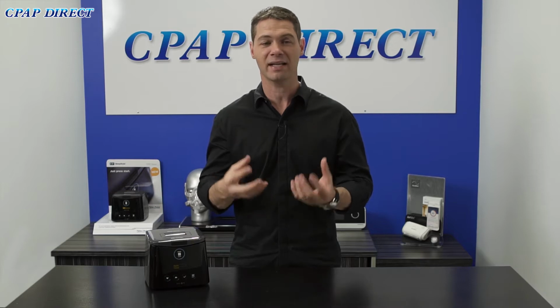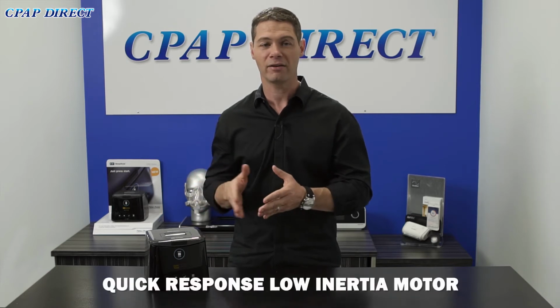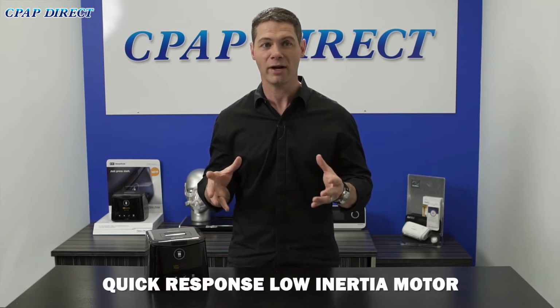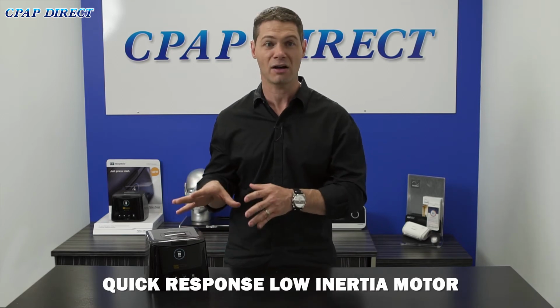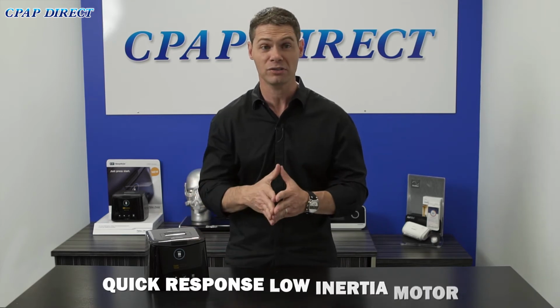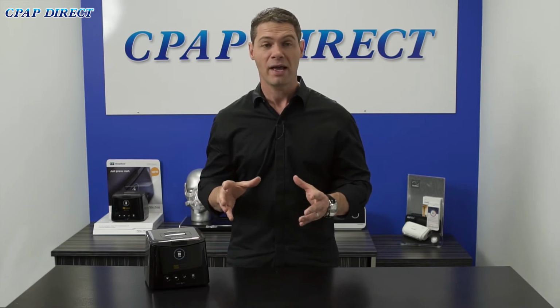So, performance-wise, the reason why it is so smooth is because they have incorporated the pressure relief side of things, the expiratory pressure relief. When you breathe out, it backs the pressure off to make it easier to exhale against the air that's coming in. That, coupled with a brand new low inertia motor that they have released, which is also lighter, meaning the whole machine is actually half a kilo lighter than the Icon was, is a real plus. And when you breathe on the machine, it feels so natural and very smooth the way the air is delivered.